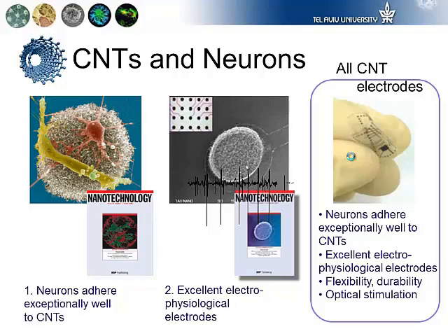Now, because of the chemical structure of carbon nanotubes, this is also a very stable material. It's very inert, and therefore in that respect very biocompatible and very stable in electrophysiological conditions. The other thing is that, again, since we're talking about electrochemistry here, the electrode, either for recording or for stimulation, ideally has to be a capacitive electrode, especially for stimulation.